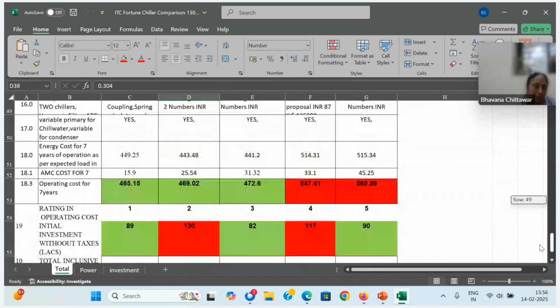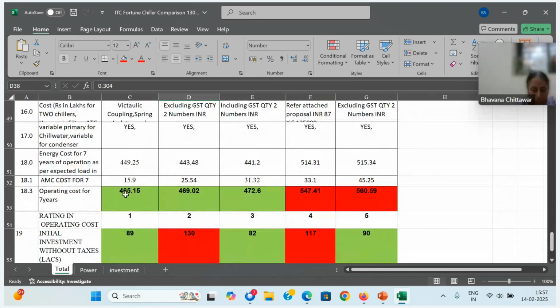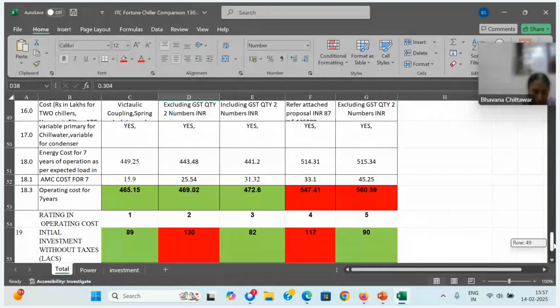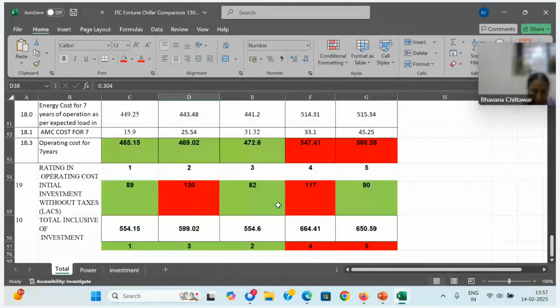So I rated the operating cost for each supplier. And for 7 years of operation, one chiller will consume 4.65 crores. Another chiller will consume 5.65. Straight away 1 crore. Whereas the 5.65 one was the preferred make, he was about to order on this make because of the investment given. The investment is almost the same, 90, 82 or something. He preferred the 90 one.